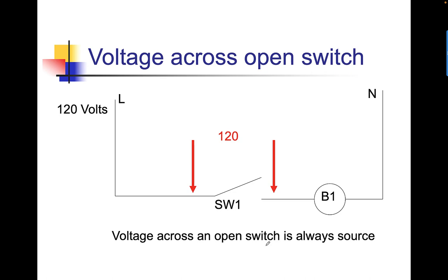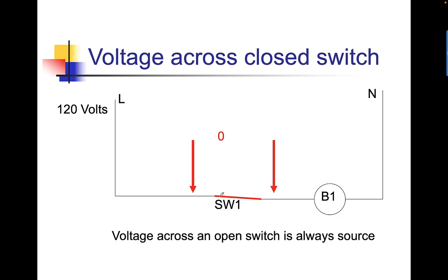In this case, I have two meter leads across the open switch. The meter is actually in parallel — my meter is here, next to the switch labeled SW1 because it's in parallel. Voltage across an open switch is always source. L1 and neutral, 120 volt source, and I'm measuring 120 volts. If I close that switch, the voltage across a closed switch is always zero. We've closed the switch and we now have zero volts because it's closed.